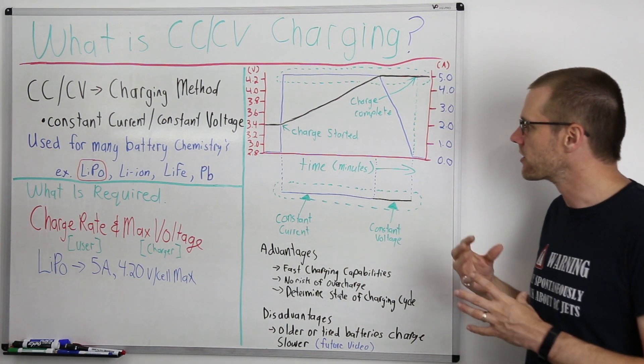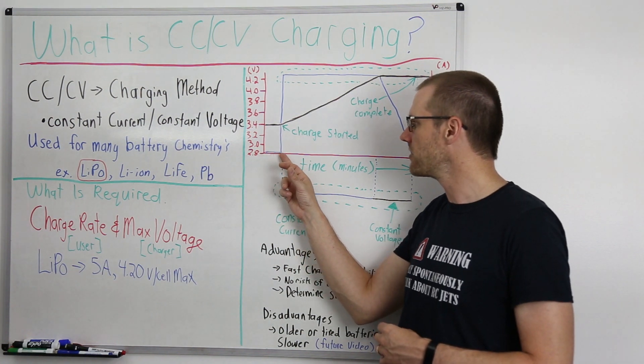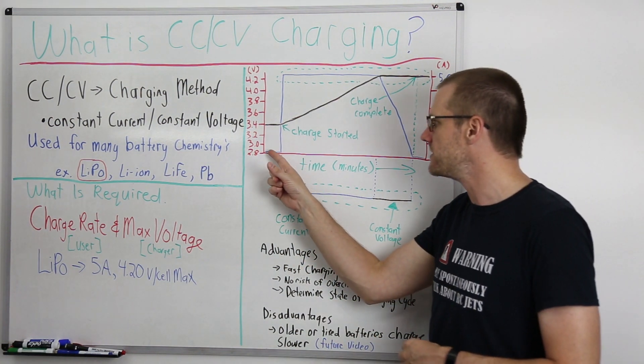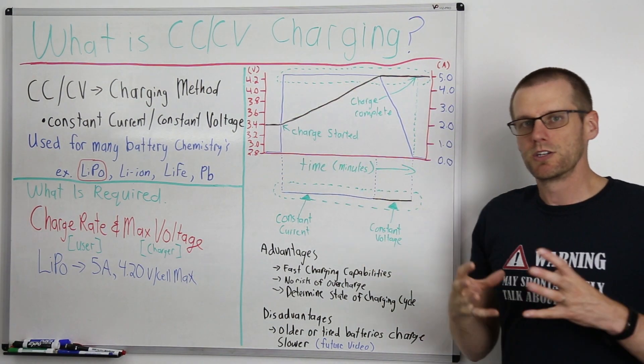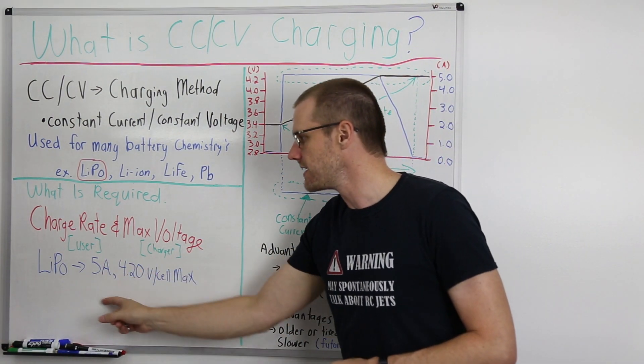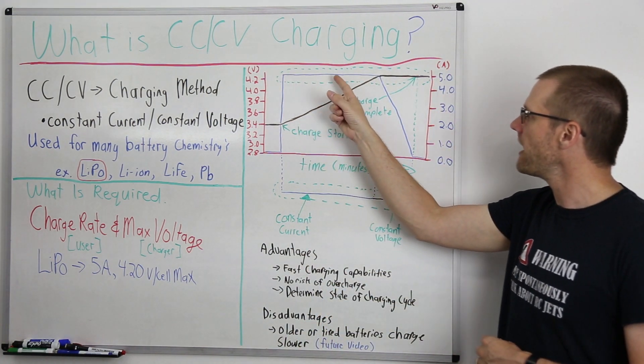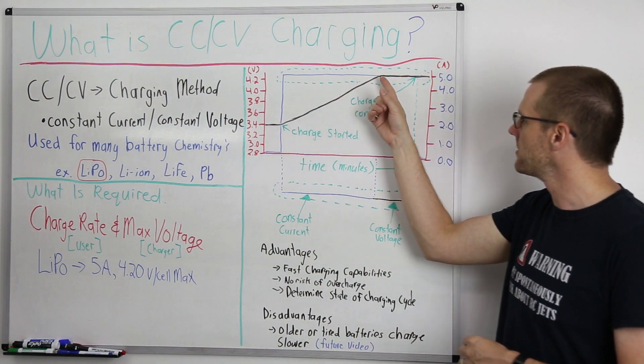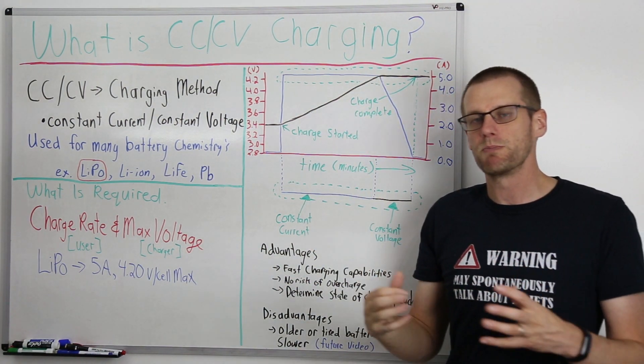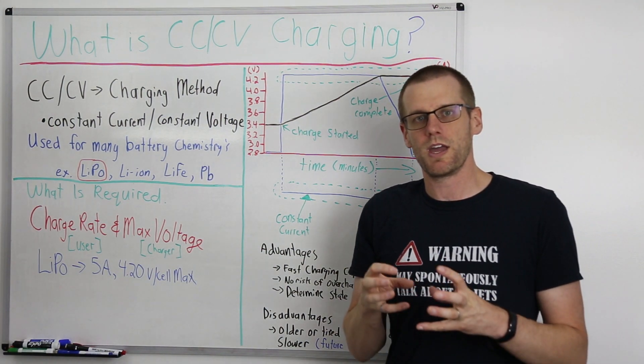Now when we look at the current, we have our pack getting all connected up and here's where we initiate our charge. We go from 0 amps all the way to our 5 amp target. This is our goal that we set up in our charger to charge at 5 amps. We're going to charge at 5 amps until this point and then from that point we end up slowly ramping down all the way to 0 amps of charge.